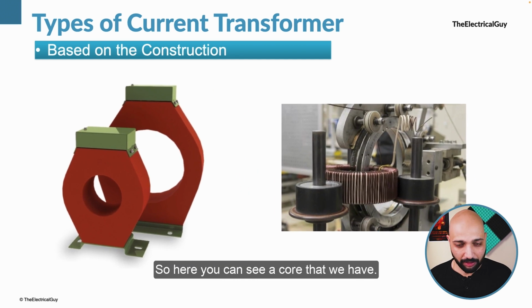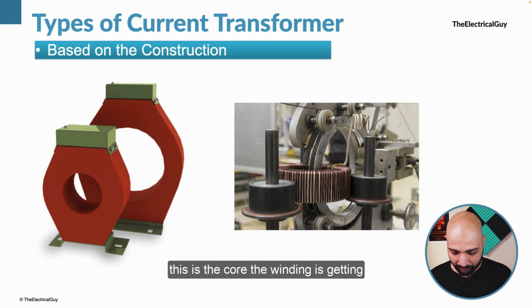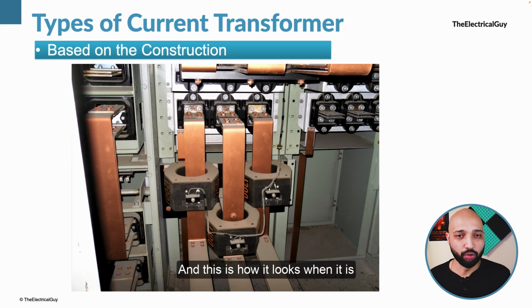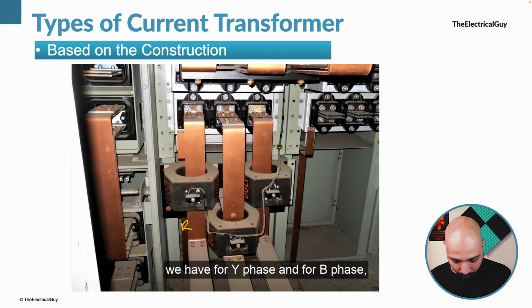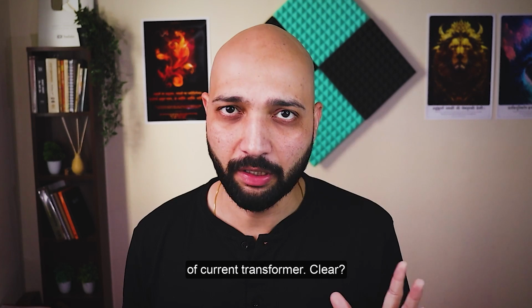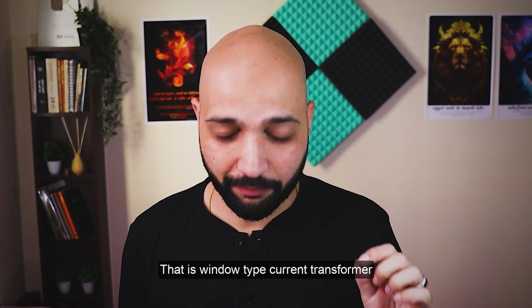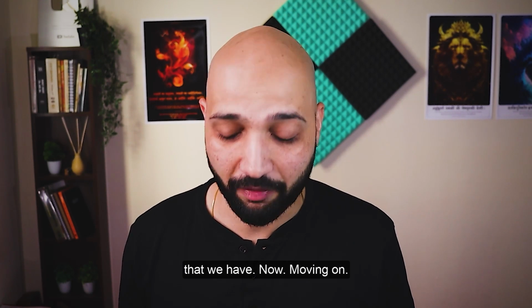So here you can see a core that we have. This is the core, and the winding is getting installed. This is a window type core, basically a circle shape. And this is how it looks when it is installed. So we have CT for R phase, for Y phase, and for B phase, window type current transformers. And this bus bar or the conductor will act as a primary winding for this type of current transformer. Clear? Understood? That is the window type current transformer that we have.